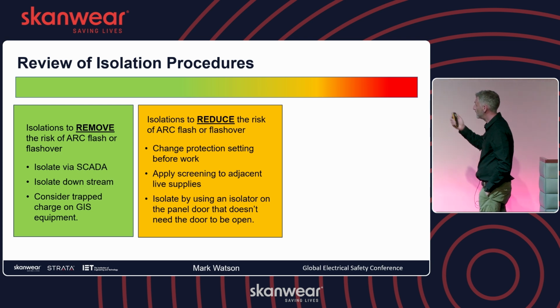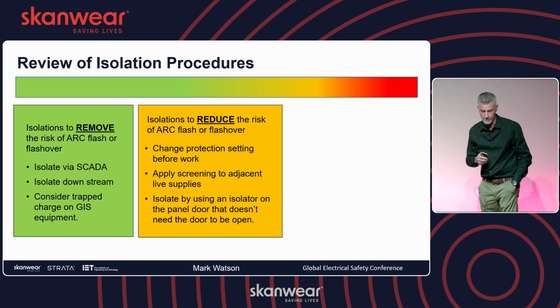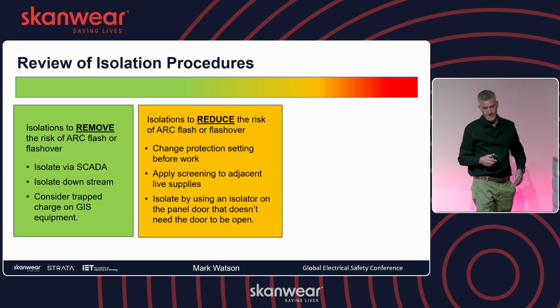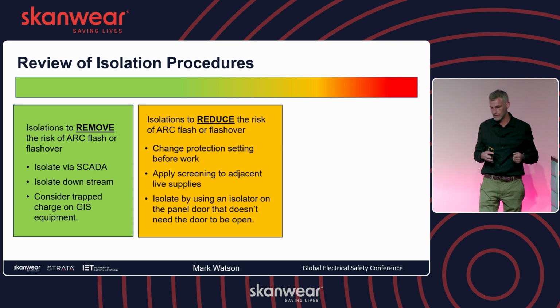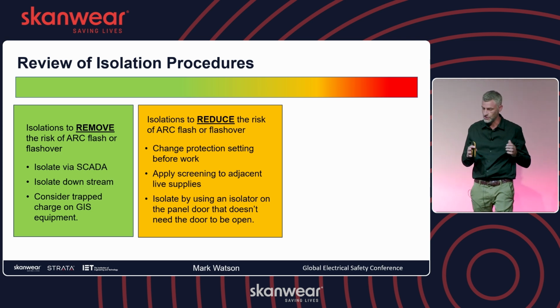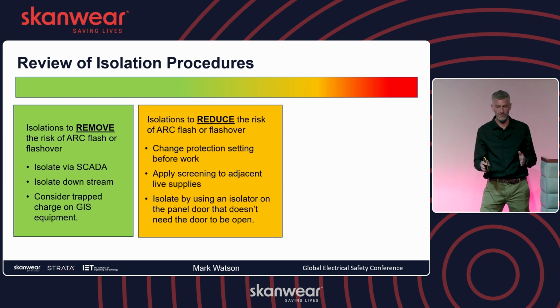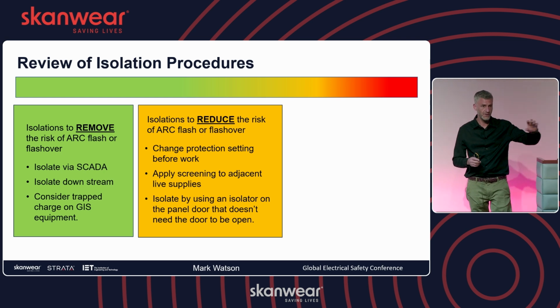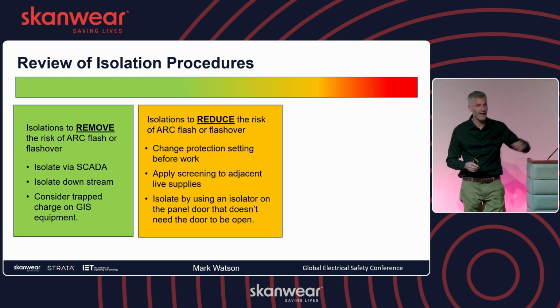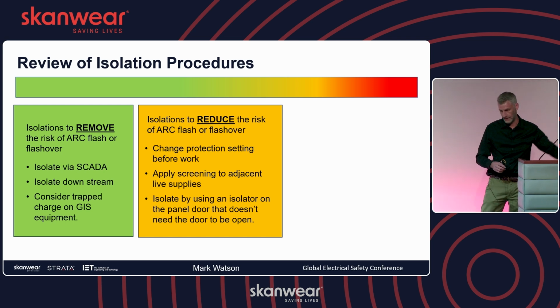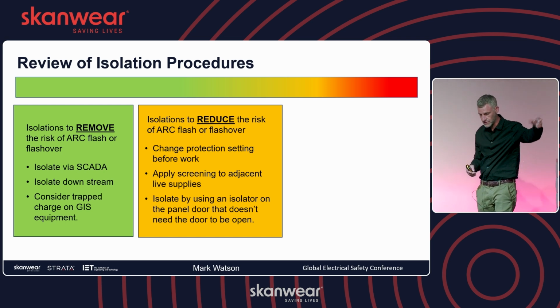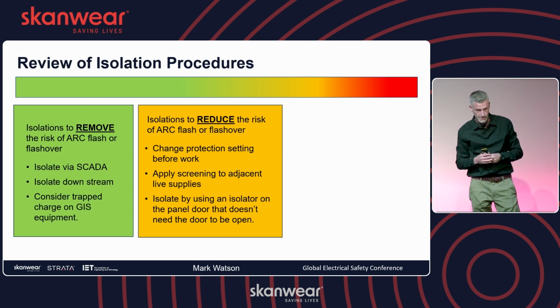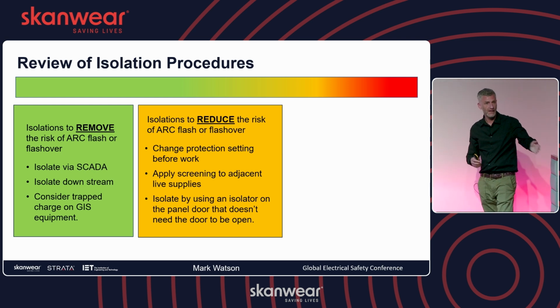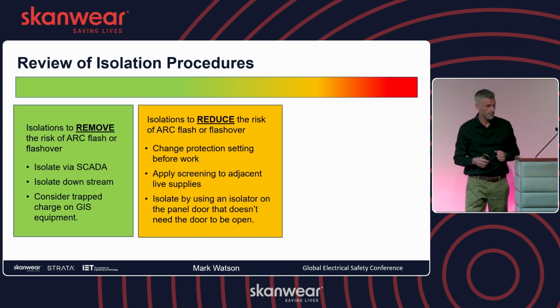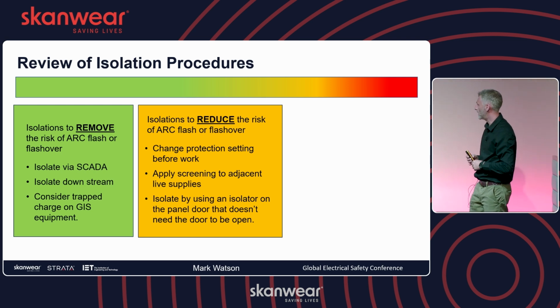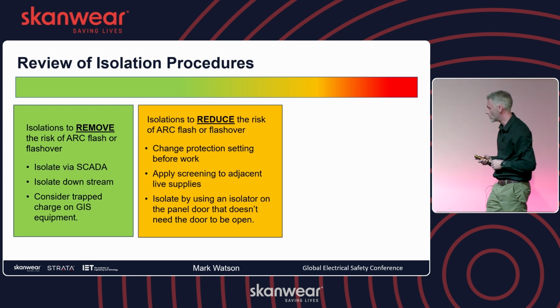And then isolate by using an isolator on another panel. So instead of opening the door like we saw yesterday - lots of people just open the door and pull the handle - let's not do that. Let's look at maybe doing a retrofit to fit a rotary isolator on the panel door, or on the panel in the next room, or the panel four panels over. Let's be able to do that from behind a closed door, away from harm's way, apply our padlocks, and we're considerably safer at that point. We're still going to prove dead when de-energized, but the bigger risk is gone.